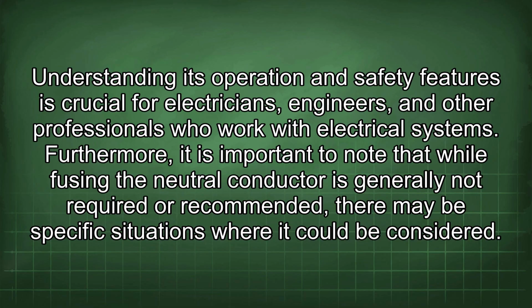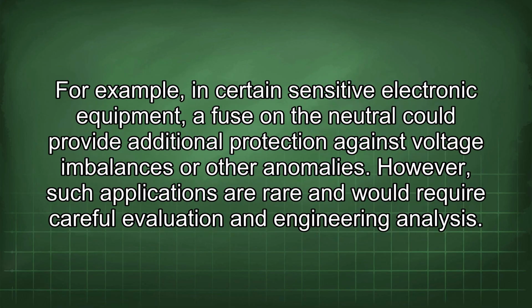Understanding its operation and safety features is crucial for electricians, engineers, and other professionals who work with electrical systems. Furthermore, it is important to note that while fusing the neutral conductor is generally not required or recommended, there may be specific situations where it could be considered. For example, in certain sensitive electronic equipment, a fuse on the neutral could provide additional protection against voltage imbalances or other anomalies. However, such applications are rare and would require careful evaluation and engineering analysis.